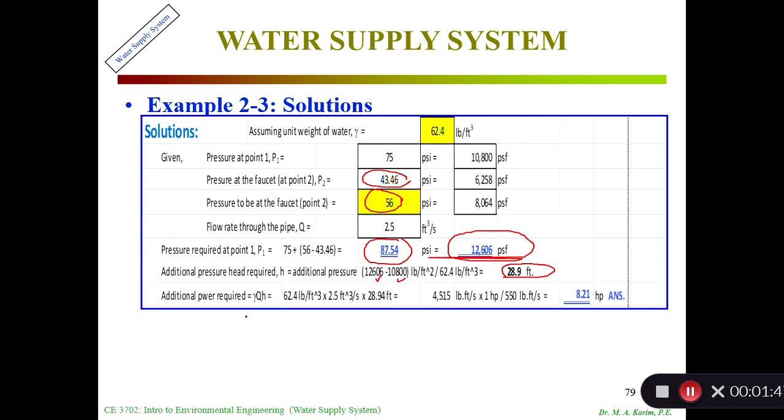From the head, if I know the power equation, power equals gamma Q H, or equal to P Q, we can find the pressure from here. If we multiply with Q, we can get it. Gamma is 62.4, Q is 2.5, and H is 28.9. We get 4515 pound-feet per second, and 550 pound-feet per second equals 1 horsepower, so I get 8.21 horsepower.